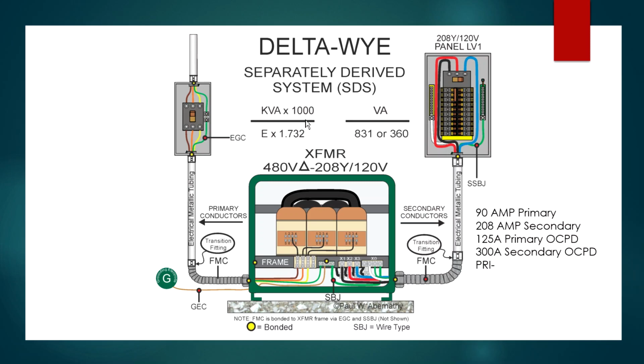Okay. So we're just kind of taking some things for granted now. All right. So we're sizing these conductors here. Now, the other thing to remember, I could have an overcurrent protection right here where they get their source from. And if that's the case, then these conductors don't have to be limited to the secondary conductor rule. They could be limited to whatever the rating is to handle the load, and we're basing it on the load that needs to be on it.